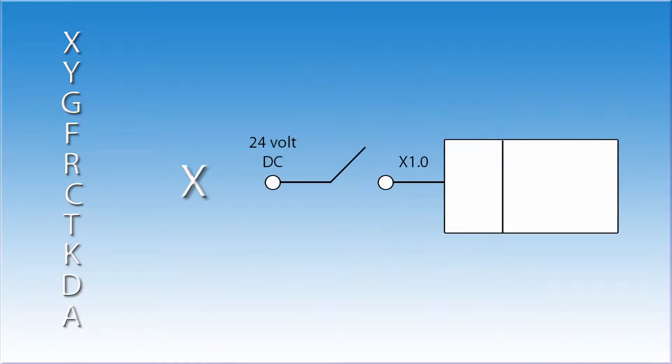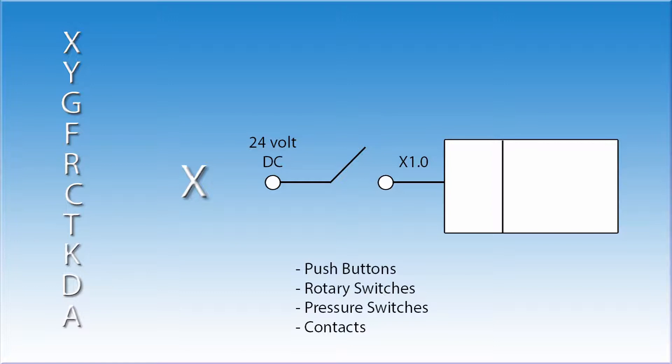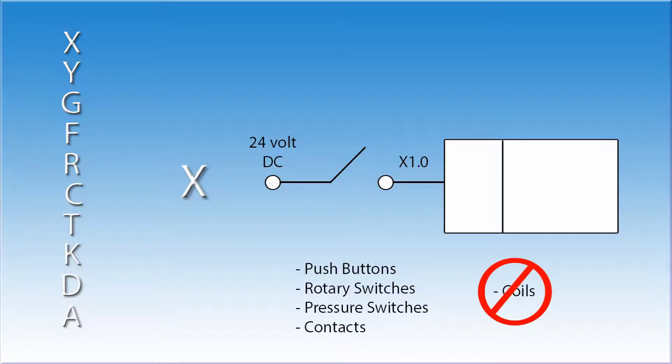Let's talk about the addresses used in the PMC. There are a number of address types. Each has a specific function. The letter X is used to designate a real world input. Remember, it's called real world because somewhere you can find a wire connected to it and measure this signal with a meter. The machine tool builder is responsible for wiring up all X value inputs. These can be items such as push buttons, rotary switches, pressure switches, or contacts. Since the X addresses are inputs, they can only be used as contacts in the ladder. You will not find them used as coils. If you are familiar with the Allen Bradley control, they refer to these as I signals.